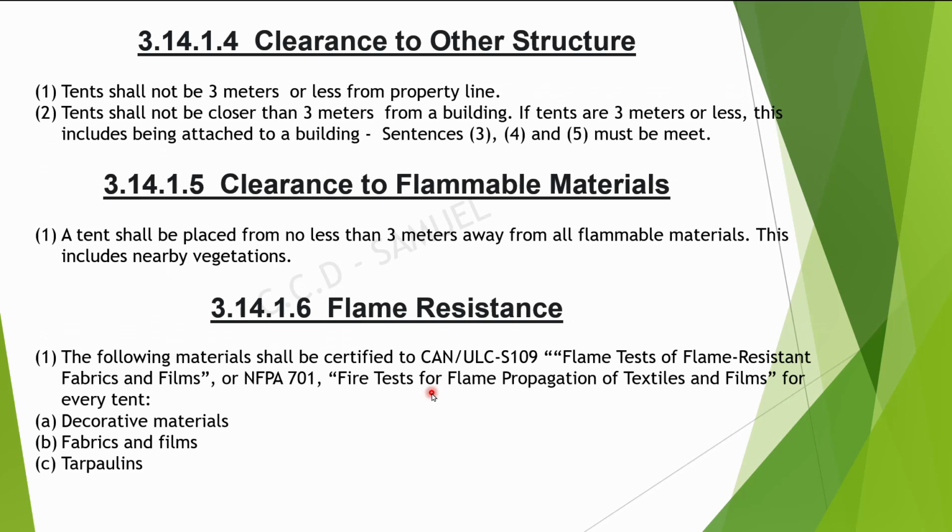Now flame resistance. The following materials, and what are these materials? Decorative materials, fabric and films, or tarpaulins, shall be certified to CAN/ULC S109 or NFPA 701.